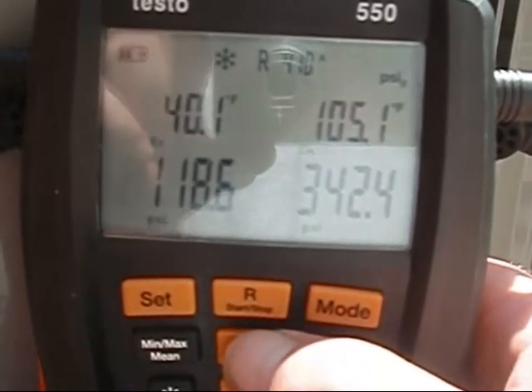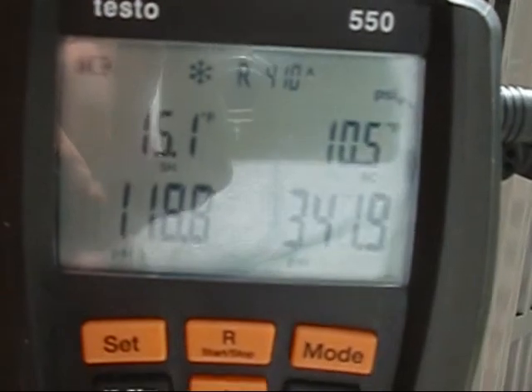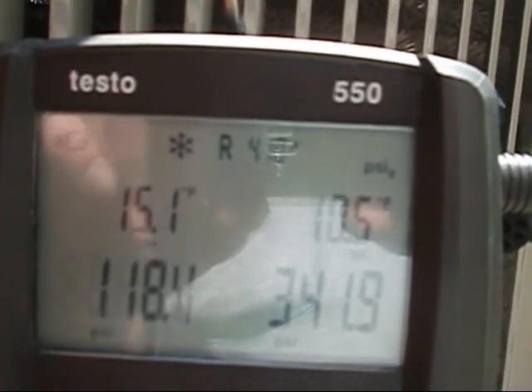Like I said, guys, we're looking for nine — we get a variance of plus or minus three. And looky there — our superheat is 15.1. Our subcooling — we were looking for nine — we are at 10. Two years later, we're at 10. I'm not going to split hairs and try to dial it in to nine. She's perfect. I think Brenda is dialed in, guys. And that's going to fluctuate a little bit when that TXV is opening and closing. I'm allowed a variance of three. So we're looking for nine — we're at 10.5. She's hanging in there, guys.